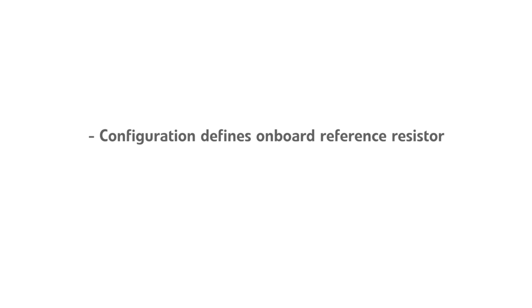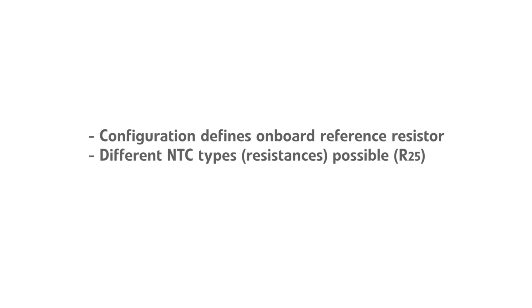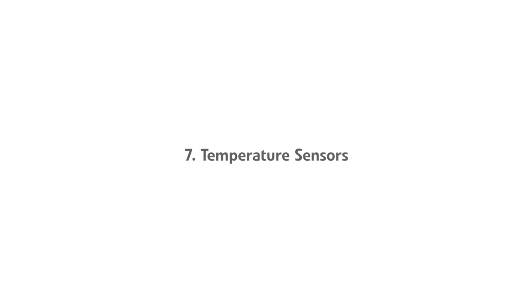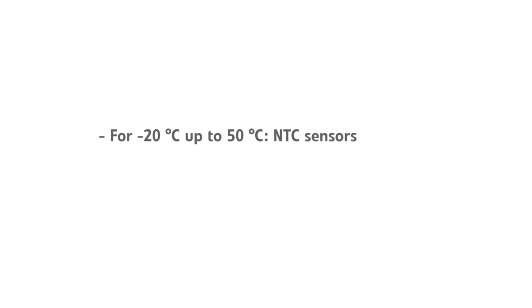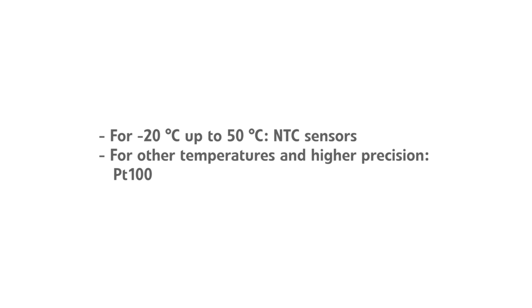This only defines the reference resistor and therefore the maximum measurable sensor resistance, not the NTC sensor type. The sensor can, for example, be an NTC 10K, which means that the resistance of the sensor equals 10 kΩ at 25 degrees Celsius. For the temperature sensor selection, the application and its temperature range dictates the kind of sensor. Generally, for temperatures from -20 up to 50 degrees Celsius, NTC sensors can be used. For other temperatures and high precision measurements, we suggest to use PT100 sensors.